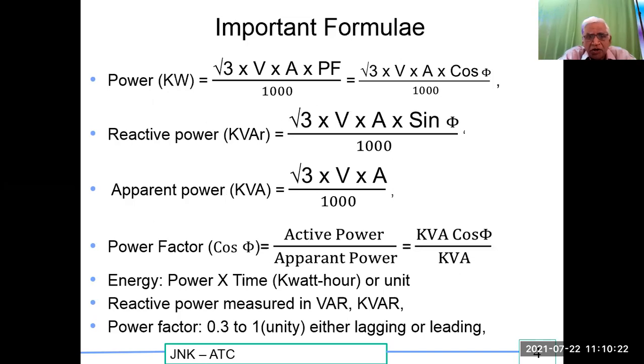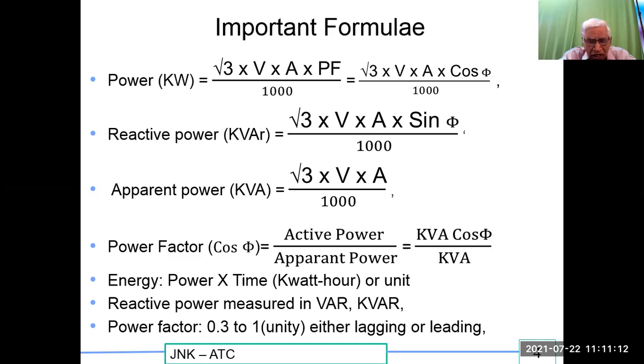Important formulas: Active power in kilowatts = (root 3 × V × A × power factor) / 1000, where power factor is cos φ. Reactive power in kVAR = (root 3 × V × A × sin φ) / 1000. Apparent power in kVA = (root 3 × V × A) / 1000. Power factor (cos φ) = active power (kW) divided by apparent power (kVA). Energy = power × time in kilowatt-hours. Reactive power is measured in VAR or kVAR — spelled VAR in capitals.